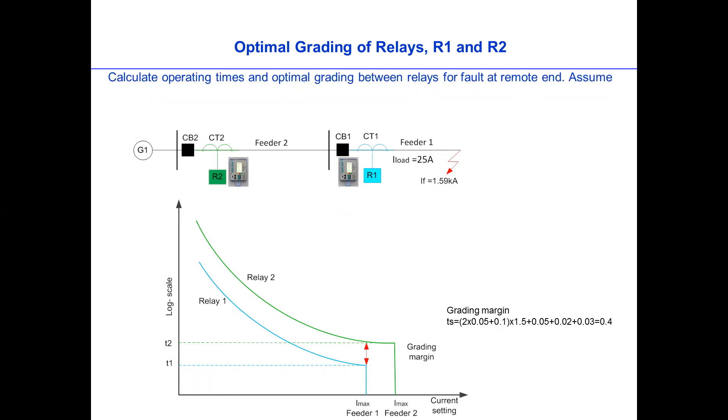How do we calculate the operating time of the relay and optimal grading between the relays for fault at remote end? How do we calculate the trip time of each relay? If we assume that the maximum loading current is 25 Amps, and the CT ratio of each relay is 100 to 5 Amps, meaning that this CT will read 100 Amps primary and 5 Amps in the secondary side.